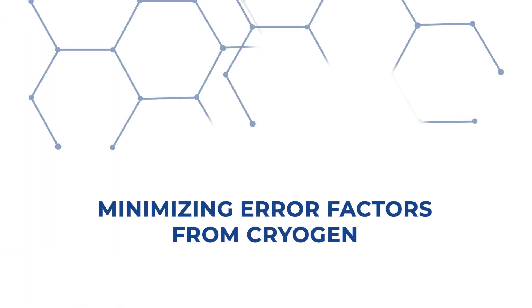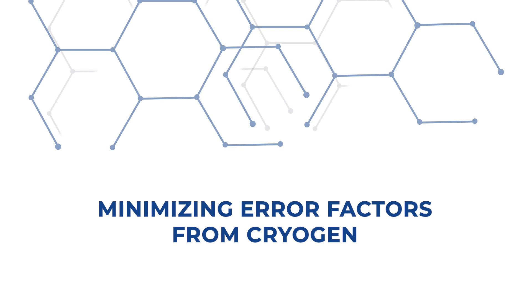Tip number five: minimizing error factors from cryogen. First, the purity of liquid nitrogen should be greater than 99.9%, since lower quality leads to higher measured saturation pressure.